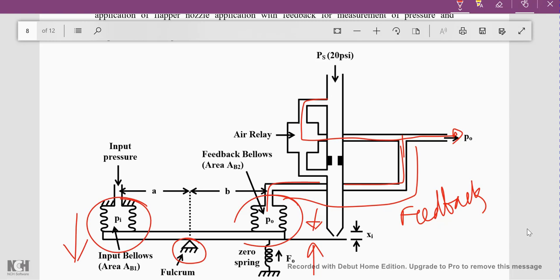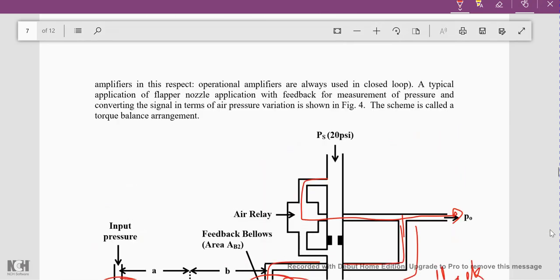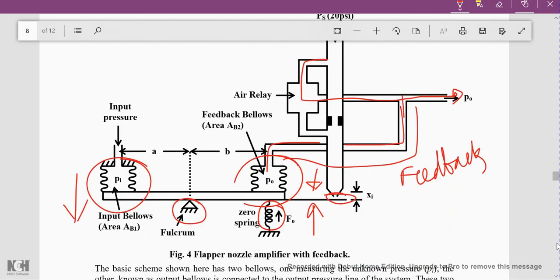When we require a constant pressure, the Xi value must be kept constant. To do that, the spring is adjusted so as to get the required displacement of the flapper, which will continuously give the required output value. But if unintended variations cause the input pressure to increase, that increased input pressure is sensed and given to the first bellow. When the pressure inside the bellow increases, it starts expanding.